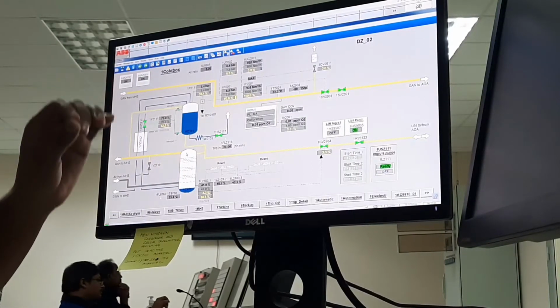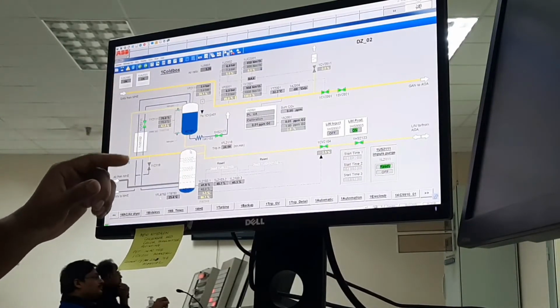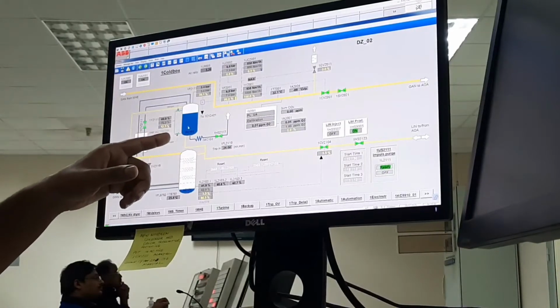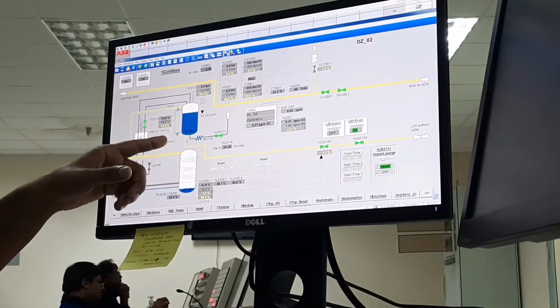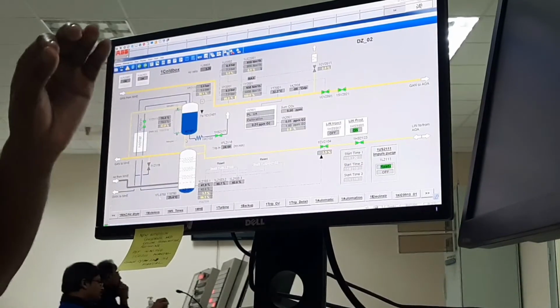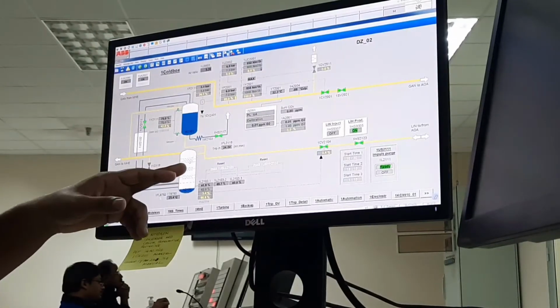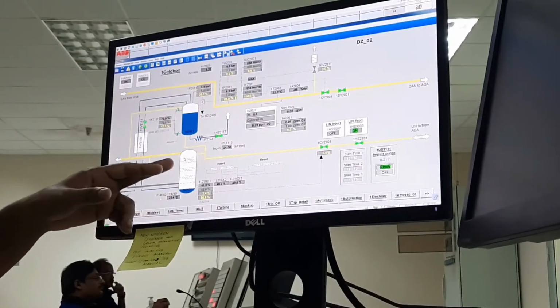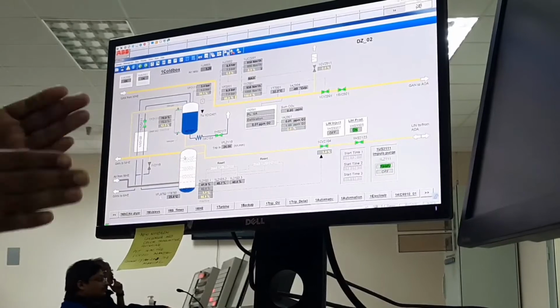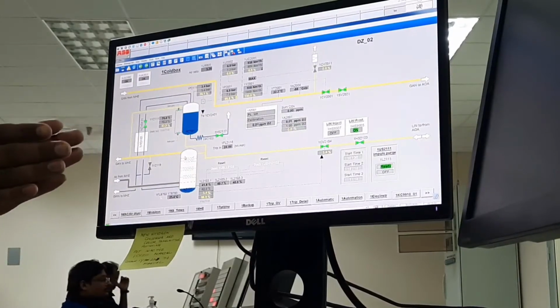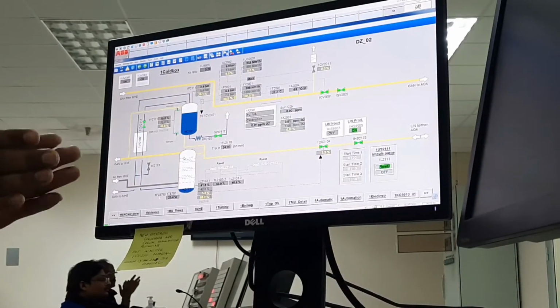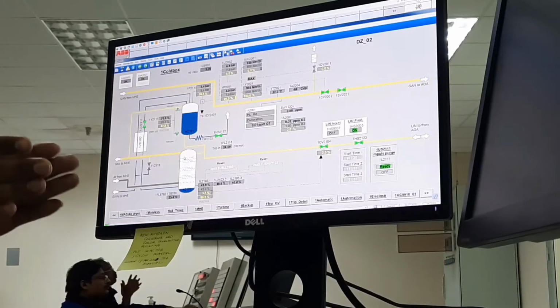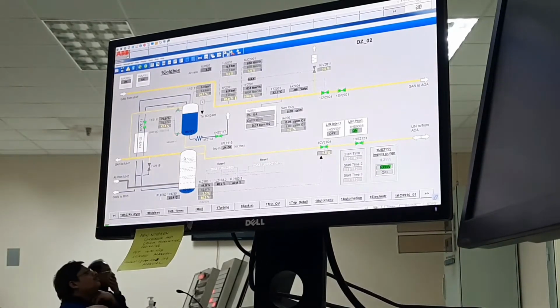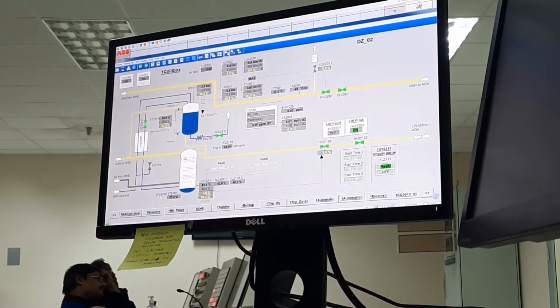Why is it reducing? You see, on this side another line is coming from the condenser. Product is coming, nitrogen is coming, and this nitrogen temperature is very low. So when one line is coming from this side and another line is going from this side, there is some counter contact. Two lines inside. When there is counter contact, there is some temperature difference and the temperature decreases, because one is very cold. Understand? Okay? Yes.